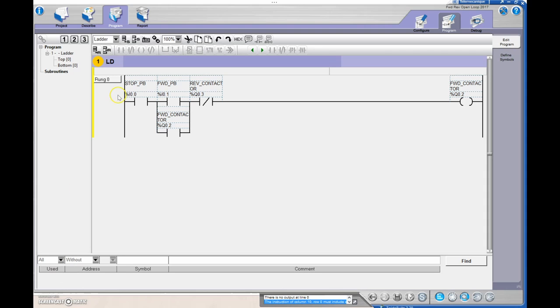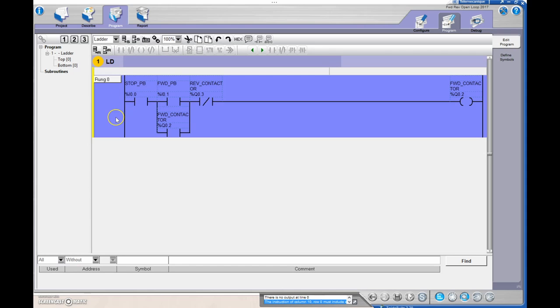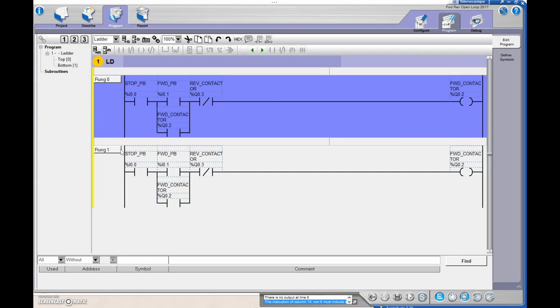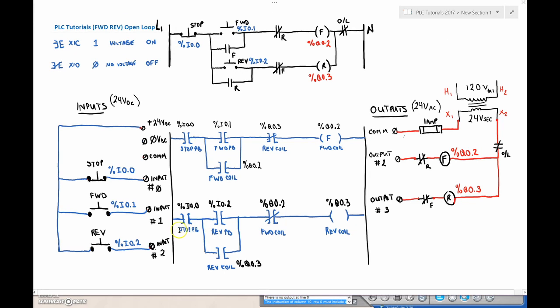We can right-click on this, hit Copy, then highlight the next position and paste, which drops in the next rung with an identical instruction for the reverse contactor. Looking at the diagram, we're going to use the stop push button multiple times — it just checks whether it's a zero or a one in the data table. The stop stays the same; the reverse push button, forward coil as XIO, and reverse coil all need to be updated.